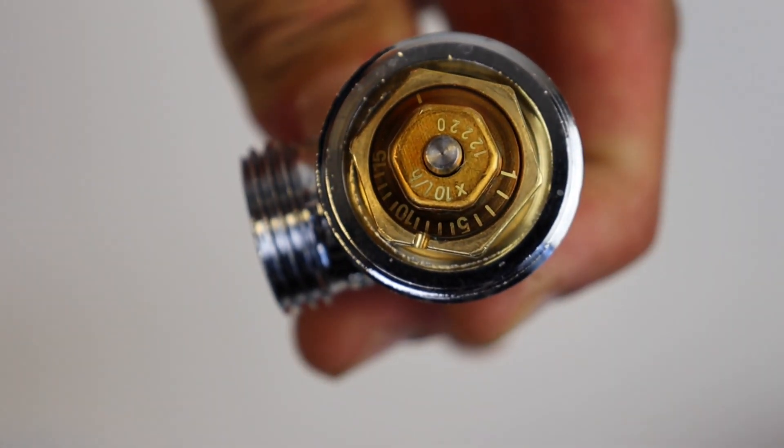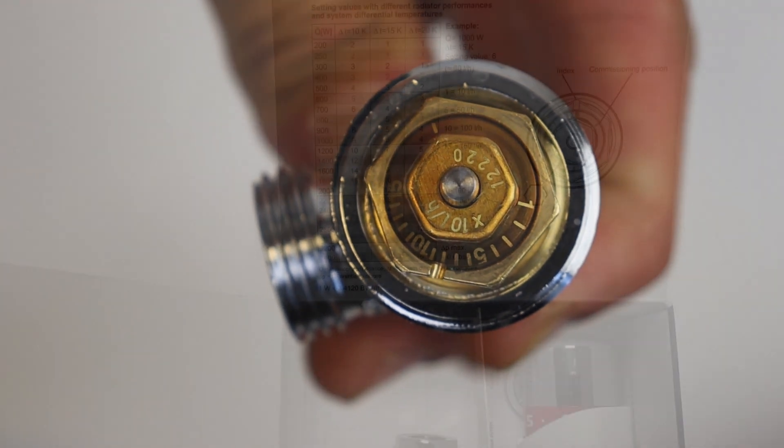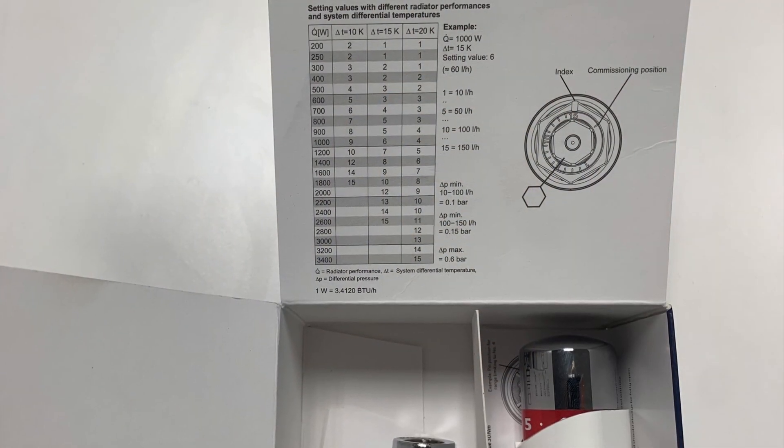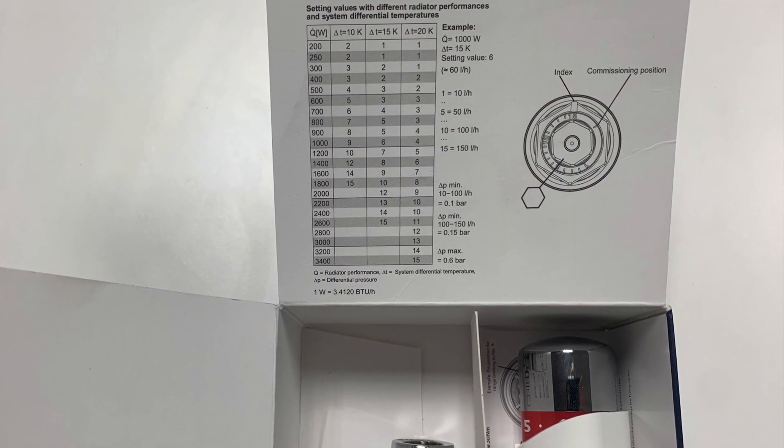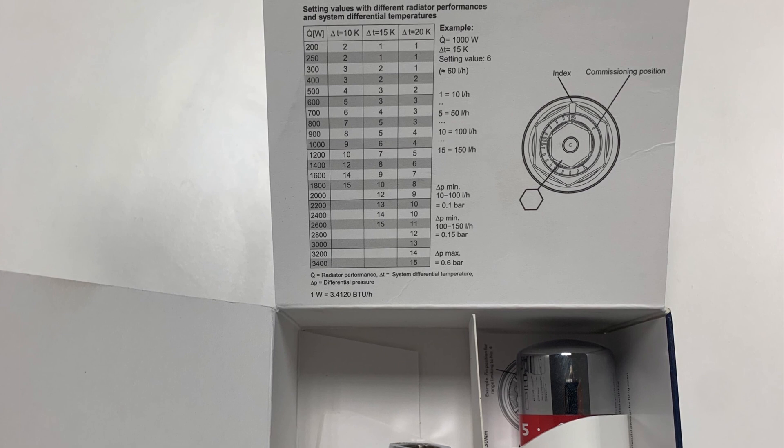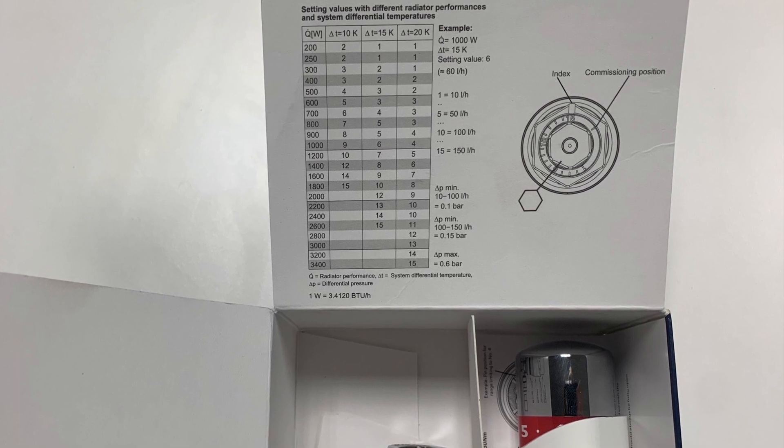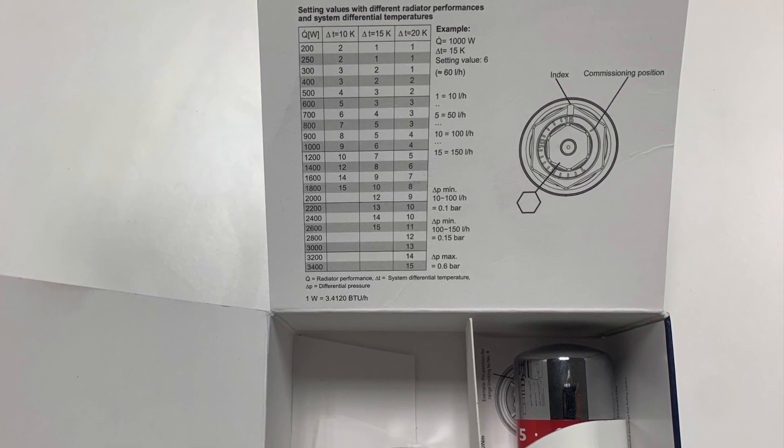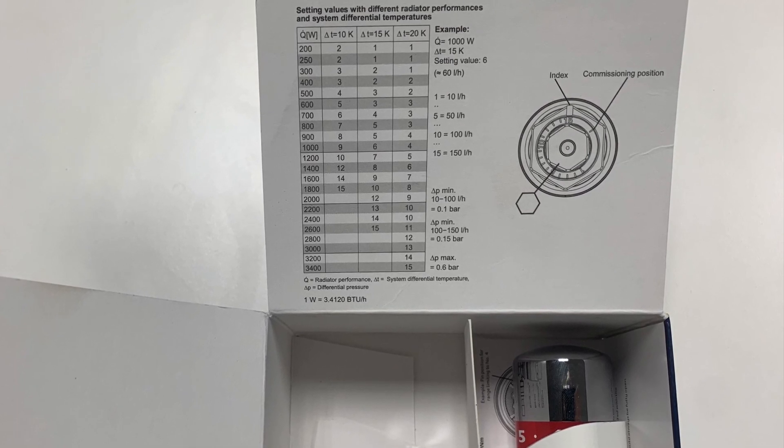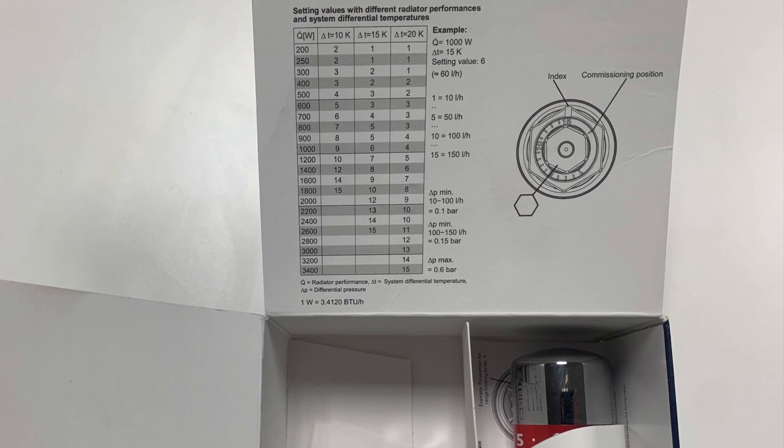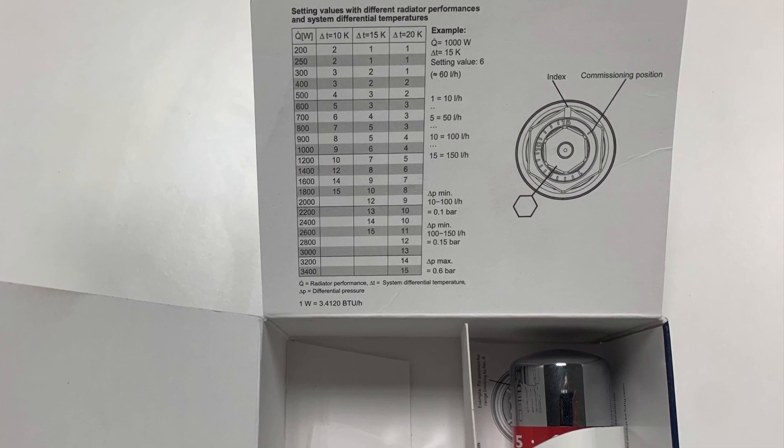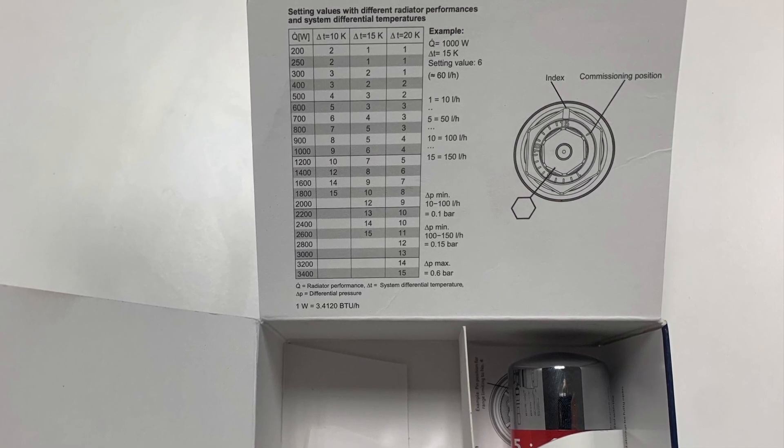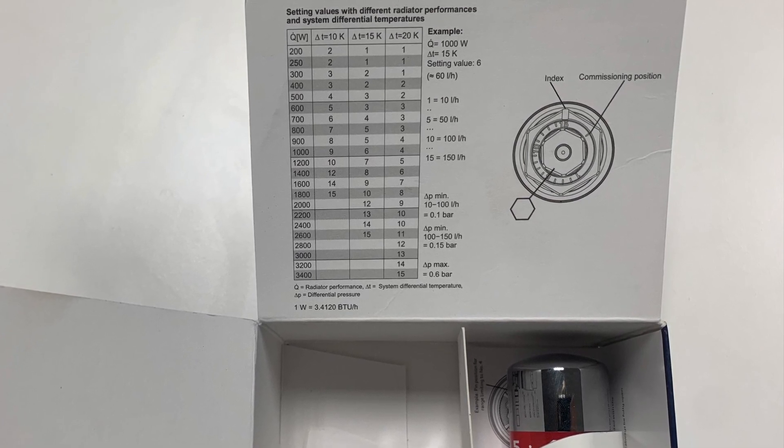There are two methods to decide what that setting should be. Firstly, the insert of the box. If you know what the output of the radiator is you choose the radiator output plus the differential temperature and you've got three options there and that will tell you what increment to set the insert to.